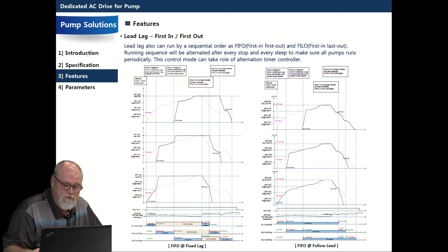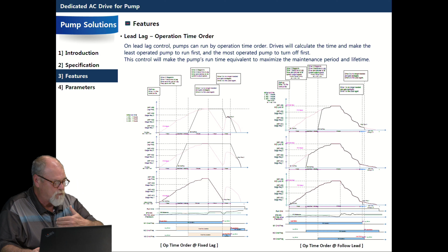This gets into the lead-lag operation order: first in, first out. If one VFD or pump has operated the longest, it's first out, and the next one brought on is the one with less operating time.